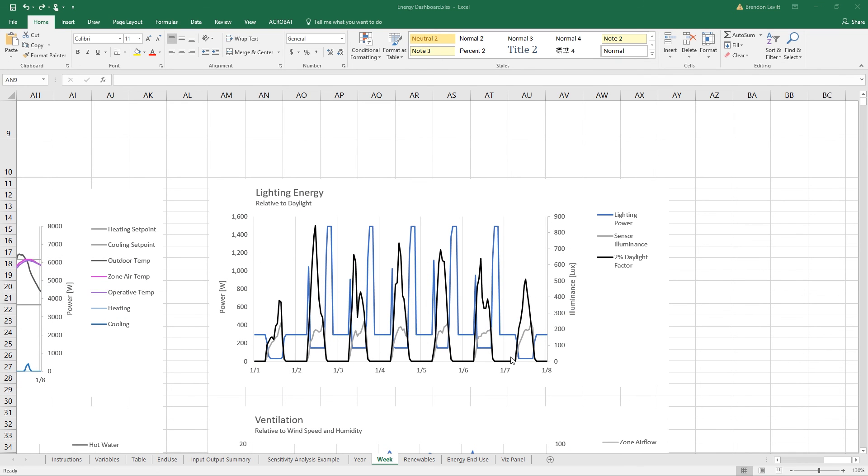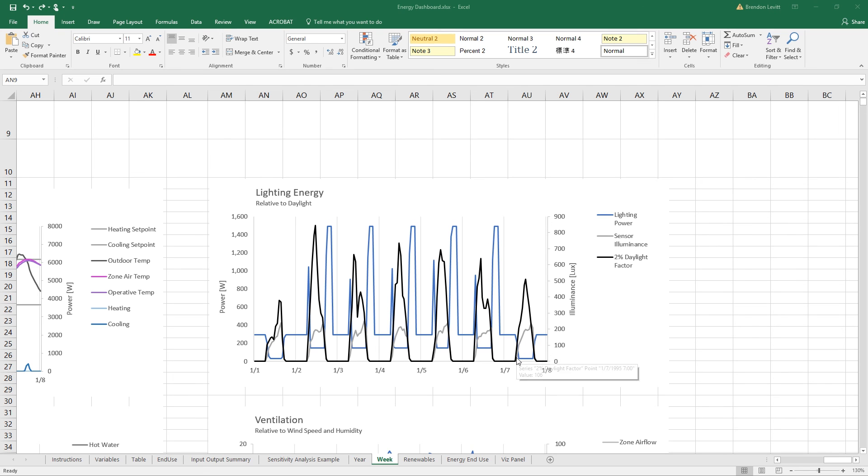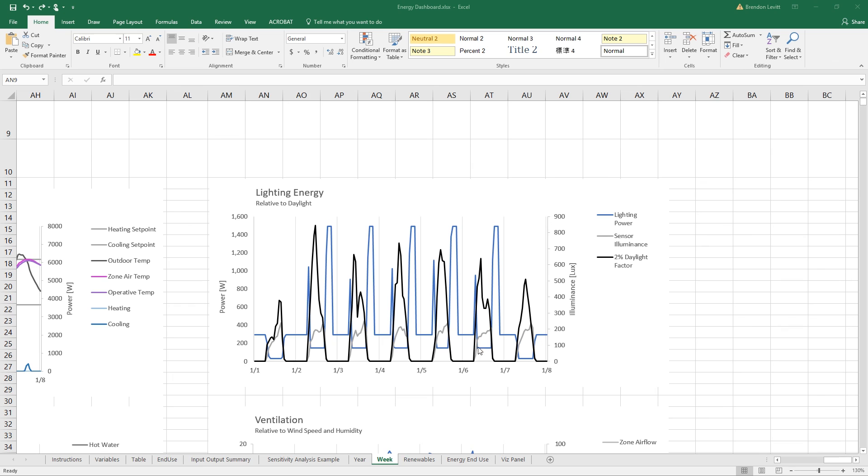So once the sensor illuminance gets above 100 lux, you can see on this side, then the electric lights start to dim down. And you can see that they're not using very much power at this time. And remember that they're set to either use zero or 10% and then dim continuously from 10%. So this is probably 10% of their total power, which is way up here.